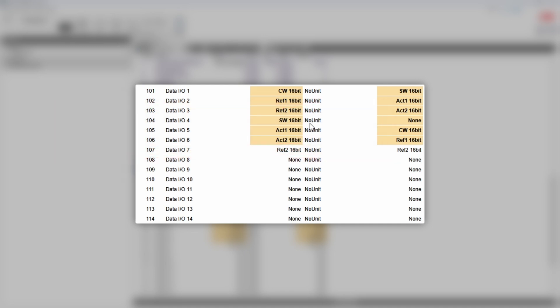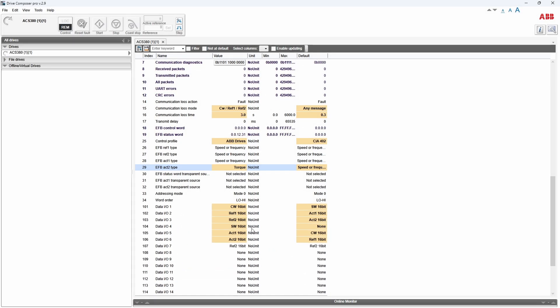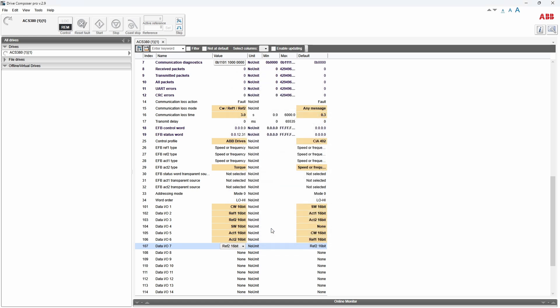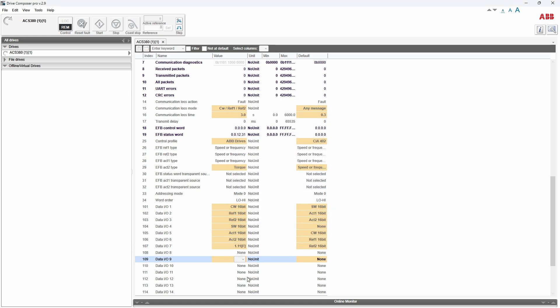You probably already see where I'm going with this. Addresses of these registers in most cases are not going one after another, which means you must send separate requests to read each register you need. And that's exactly why you have these 14 data IO registers. The first three by default are mapped to control and reference purposes, the next three are mapped for status and feedback, and all others you can use for your own needs — for example, to get DC bus voltage or status of digital inputs of the drive.